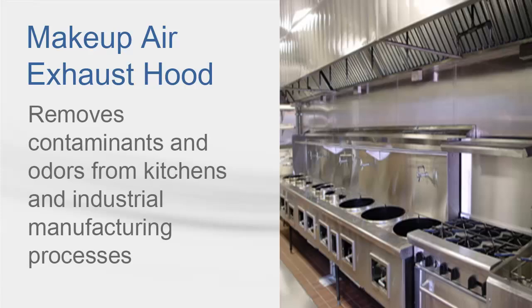Why are we concerned about pressurization? Exhaust hoods are commonly applied in kitchens to remove airborne grease, combustion products, fumes, smoke, odors, heat, and steam by evacuation of the air from the space. They can negatively pressurize a space, which will prevent contaminants from entering adjacent spaces like the dining room. They may also be used for industrial or manufacturing processes to remove contaminants and odors from the air, specifically in painting booths and where chemicals are heavily used.